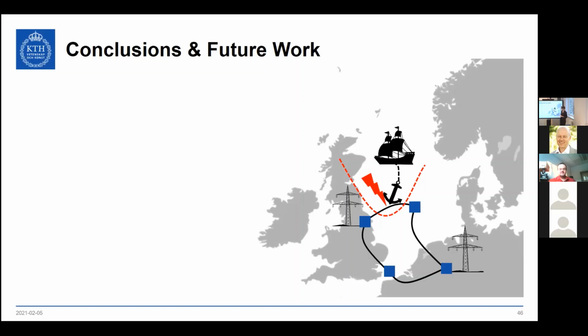We didn't have specifications for sampling times, so the IED is sampled at 50 kilohertz. That value was chosen based on previous publications in the literature suggesting that as a minimum requirement. That's how it is in the open source prototype; you can change it. Obviously all the simulations need higher sampling, so you can capture the traveling waves accordingly.